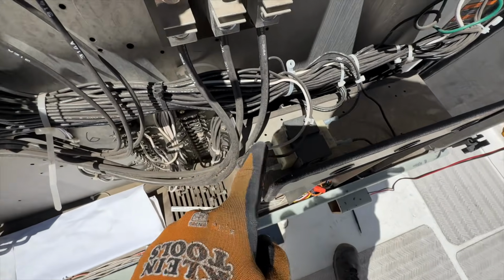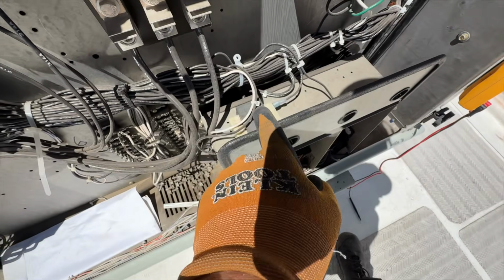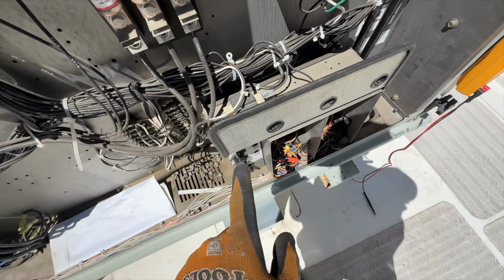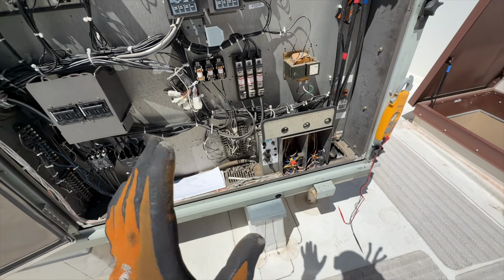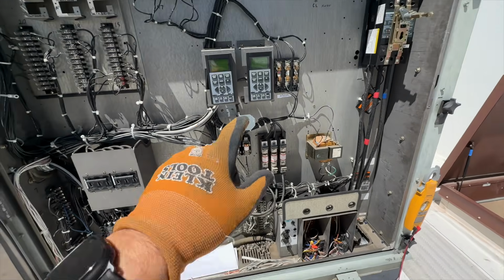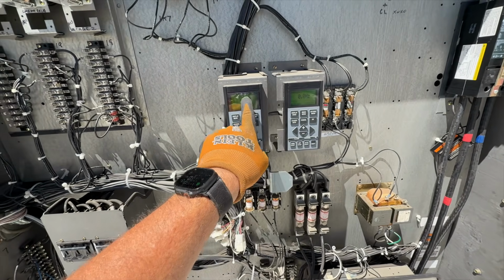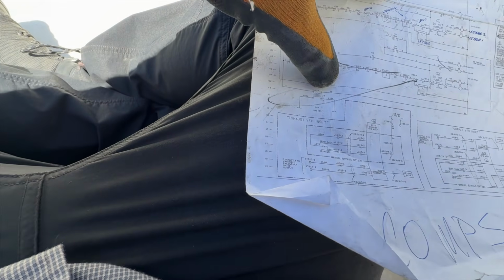I have no line voltage to this transformer, therefore there's no voltage coming out of it. The inside units are not functioning, and I only have one of these operating. Our transformer is right here, down here, okay? So it's 115 volts, steps down to 24 volts, which is going to control pretty much everything.